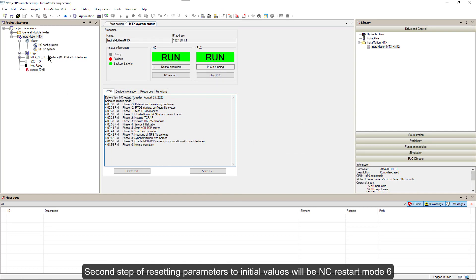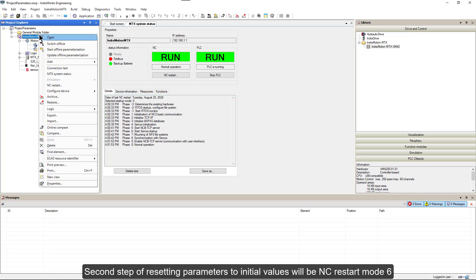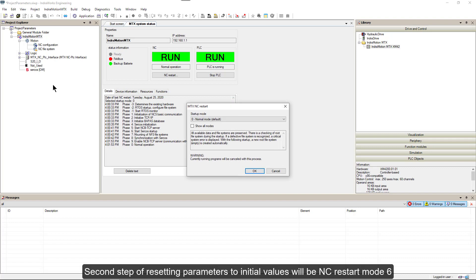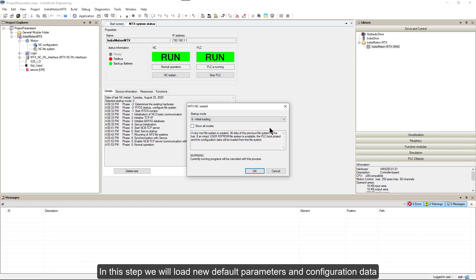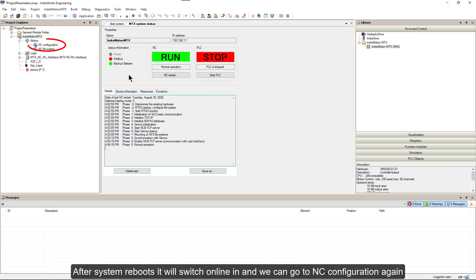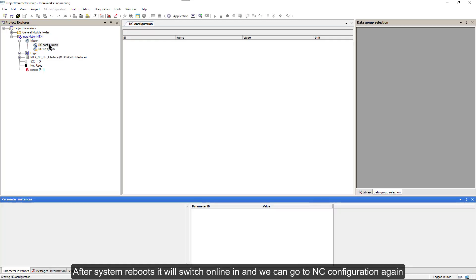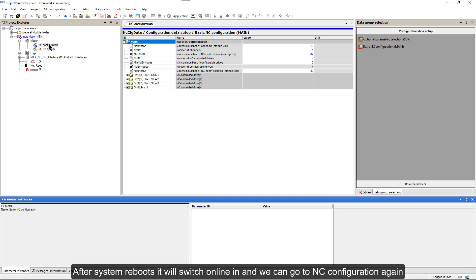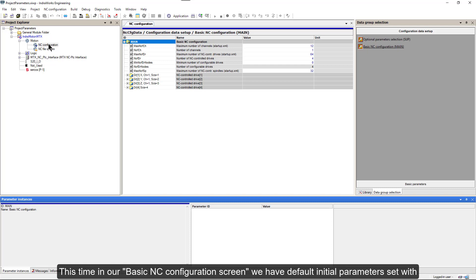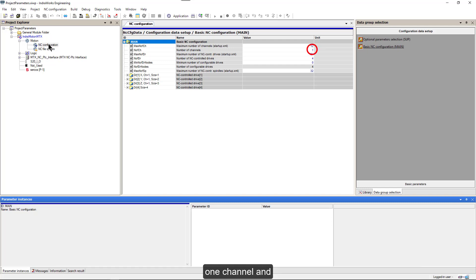Second step of resetting parameters to initial values will be NC Restart mode 6. In this step, we will load new default parameters and configuration data. After system reboots, it will switch online and we can go to NC Configuration again. This time in our basic NC Configuration screen, we have default initial parameters set with one channel and four NC Controlled Axis.